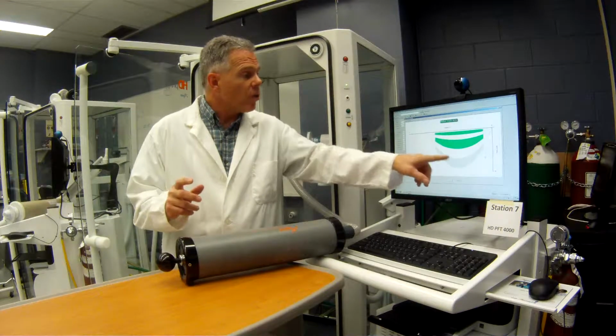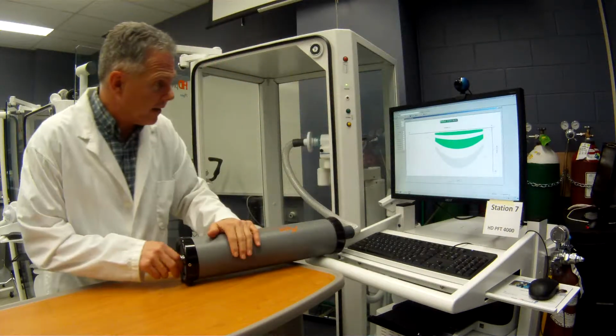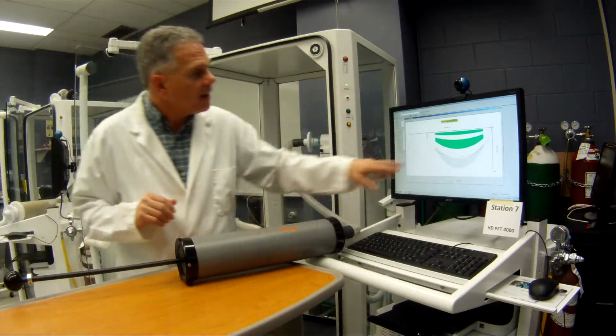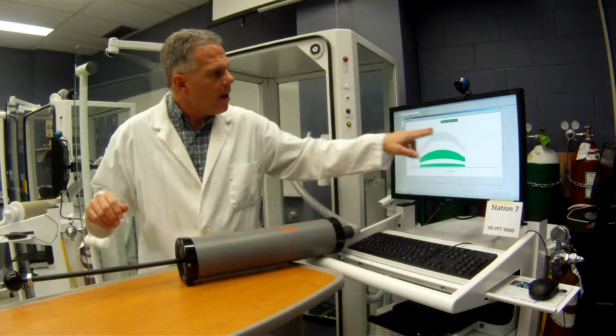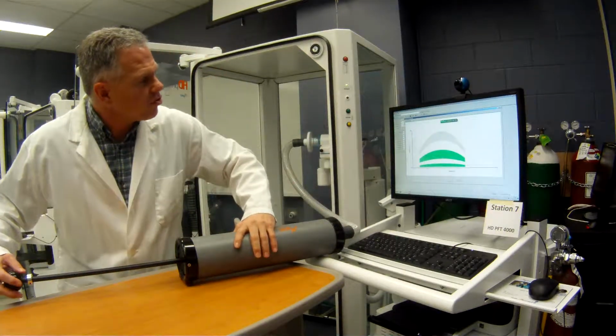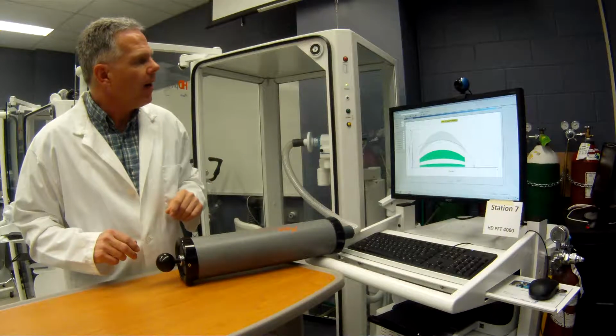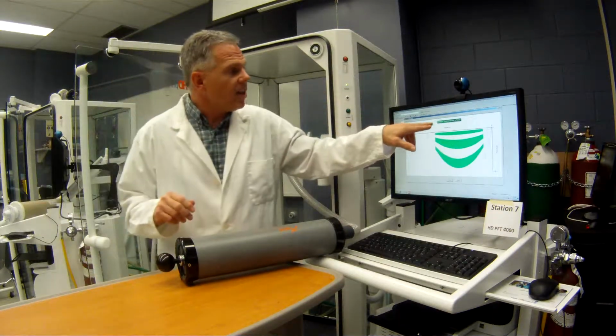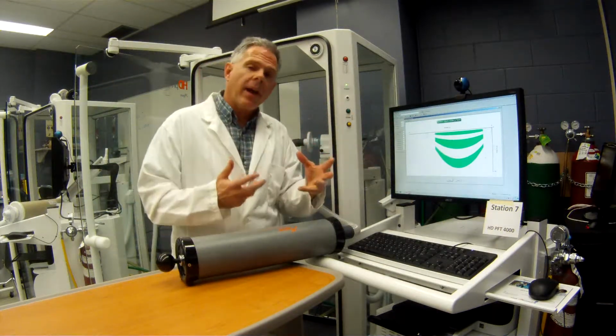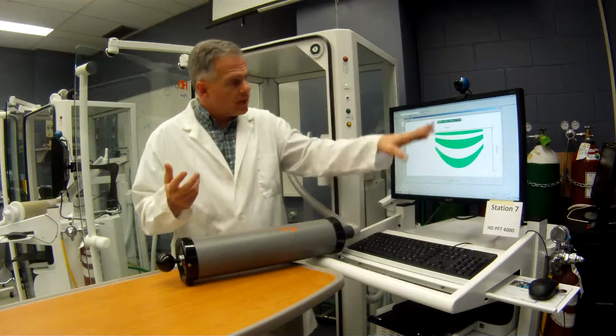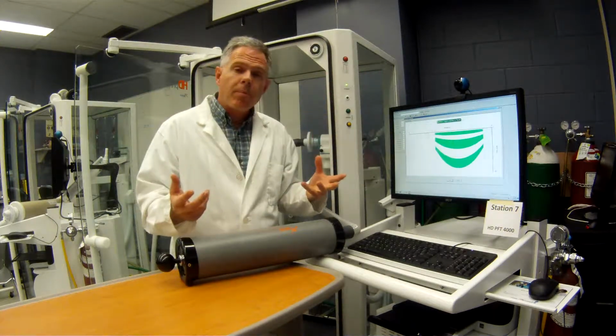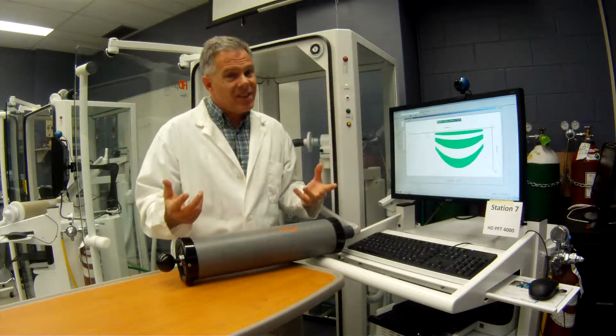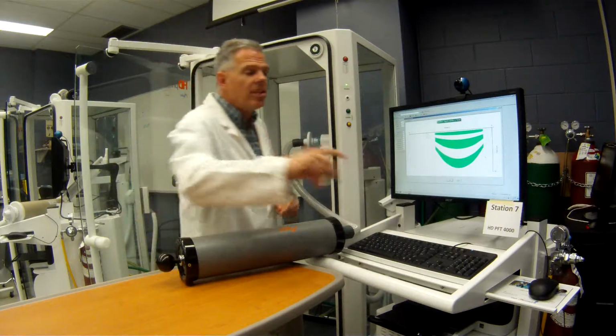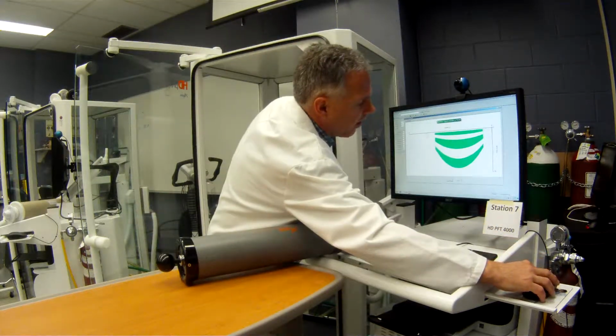So far, so good. Now we've got to get a high flow rate. All right, I don't think I quite got it fast enough. And now we're going to do the expiratory stroke. All right, okay. So this tells me now that I can keep going, or I'm finished because we're all in green, it's calibrated properly, so we're actually finished doing our calibration. But now we need to do our verification. All right, so we're finished with that.